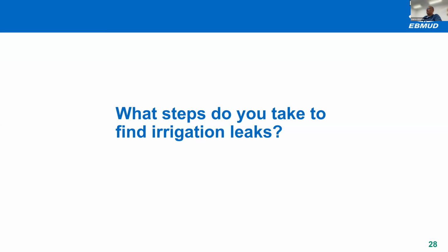Listen to the backflow. Listen to each device. Visually check. If you turn off the backflow for a matter of like 30 seconds or maybe a couple of minutes, and you turn it back on and you hear flow, at least that recharges the line, then that tells you you've got something downstream. The longer that it's off, obviously it'll do that. But if it takes a long time to recharge that line, that tells you you've got a lot more flow going through there. That's a trick from a guy who's been doing backflow testing for about 20 years. Nice. That's a good tip.